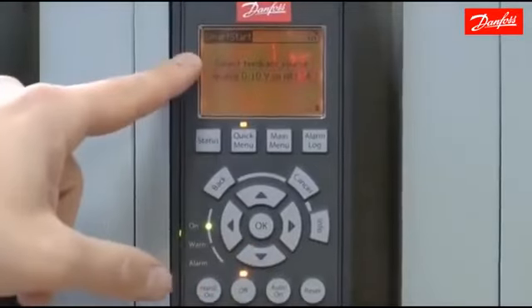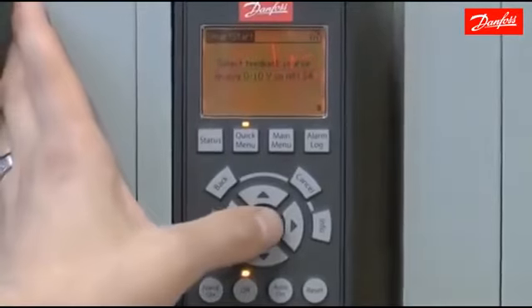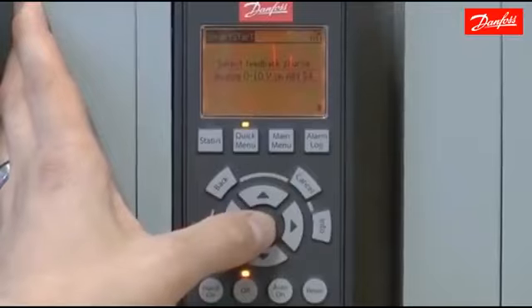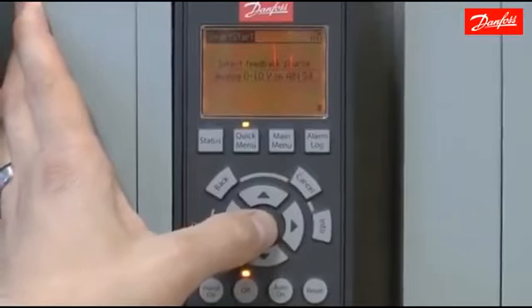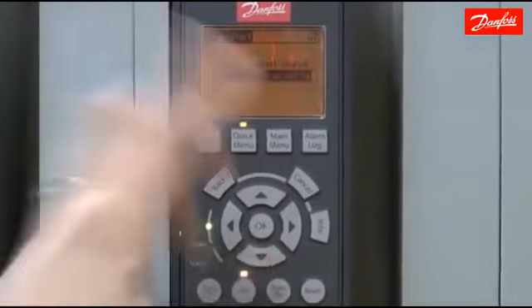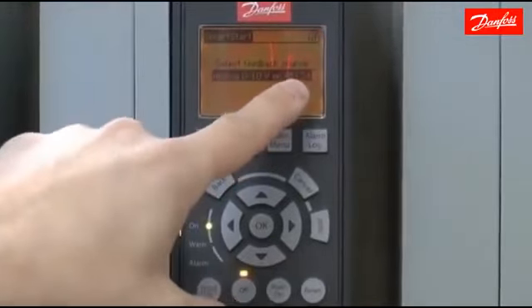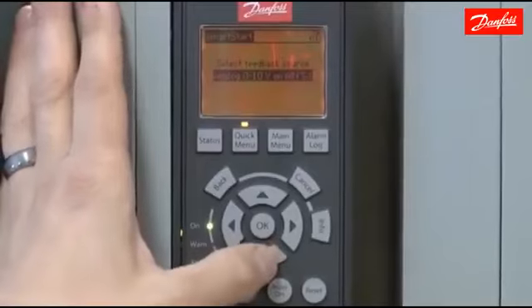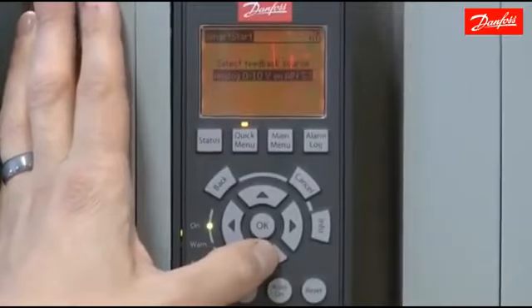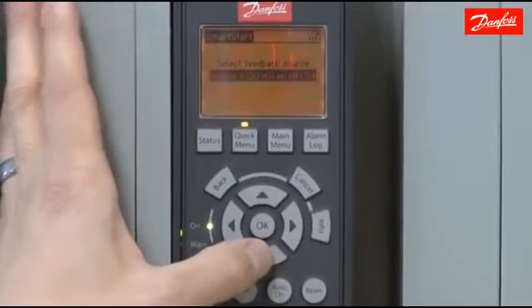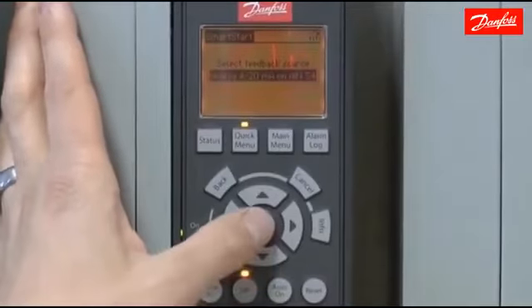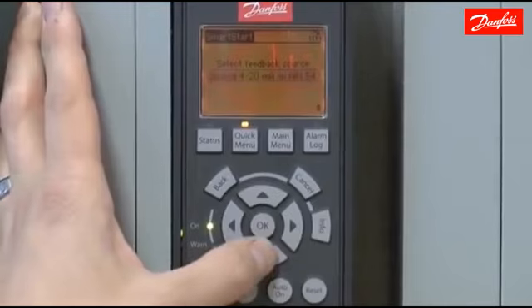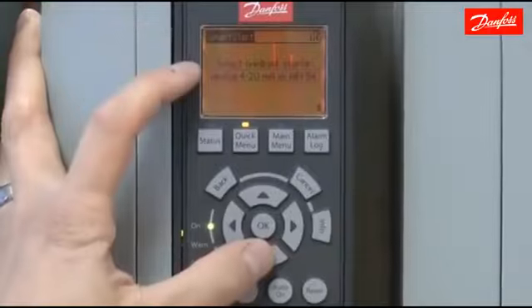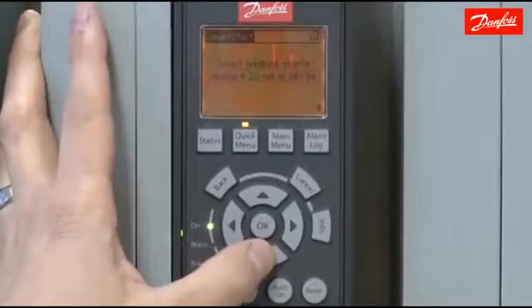The feedback source. This is where you tell the drive what type of transducer you're using. We have choices of 0 to 10 volt connected on analog input 53 of the VFD. 0 to 10 volts on analog input 53, 4 to 20 milliamps on analog input 54. I'm going to choose that because the particular transducer I'm using for this application is a 4 to 20 milliamp transducer.